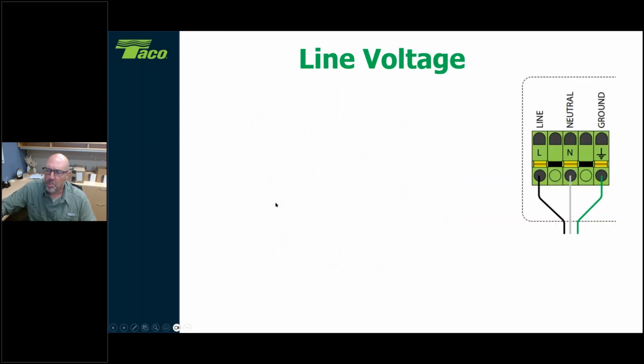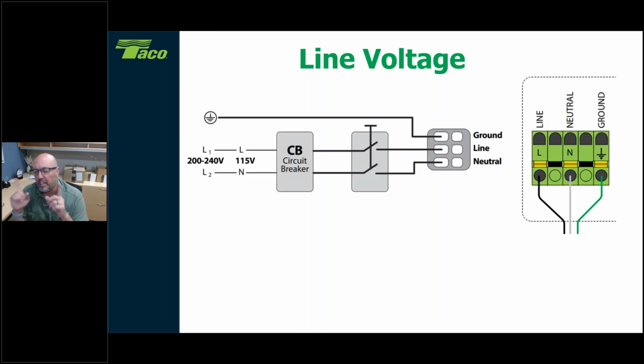All right, so bringing line voltage into this circulator. If you look at the instruction sheets for this circulator, we have these listed between 110 volt up to 277. Same circulator, but not all of them are 110 to, I'm sorry, not 277. I was thinking of a zone valve for a second. 240 volt. So you bring your line voltage in to our circulator here. You've got your circuit breaker, and you've got a safety switch there.